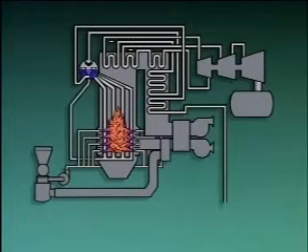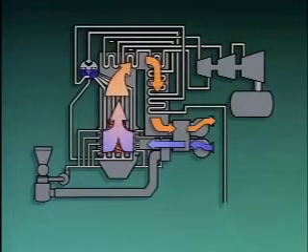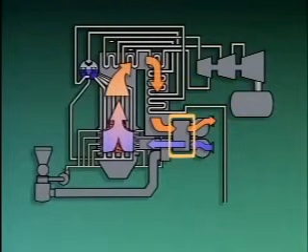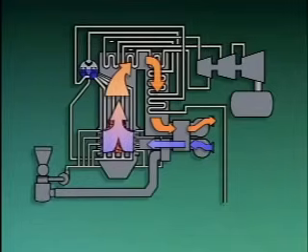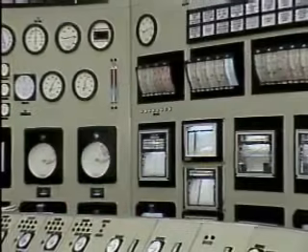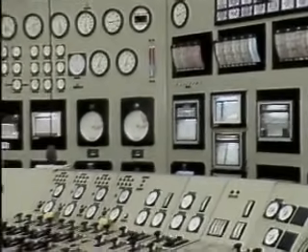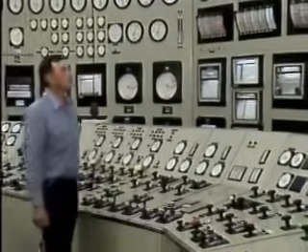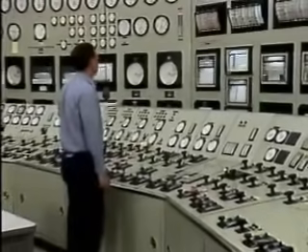Harmful byproducts are kept under control in the boiler by proper operation. For example, sulfuric acid — which is very corrosive — can form on the air preheater when sulfur trioxide in the combustion gases combines with water. To prevent acid from forming in the gas flow path, combustion gas temperatures are kept above the dew point. The dew point is the temperature at which water vapor in the gas flow path will condense into a liquid. If the water vapor does not condense, the danger of corrosion to the air preheater is greatly reduced.